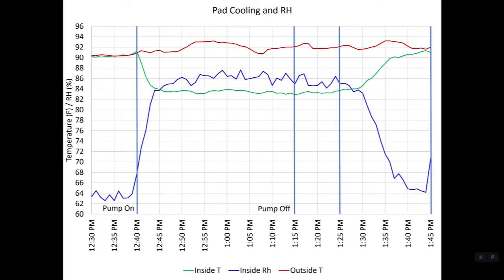It took a full 30 minutes for that pad to dry out. The point here is that when we run the pads off of a 10-minute timer, since it takes longer than 10 minutes for the pads to dry when we turn off the pump, running them off a 10-minute timer typically doesn't affect much when it comes to cooling or the humidity produced by a pad system.